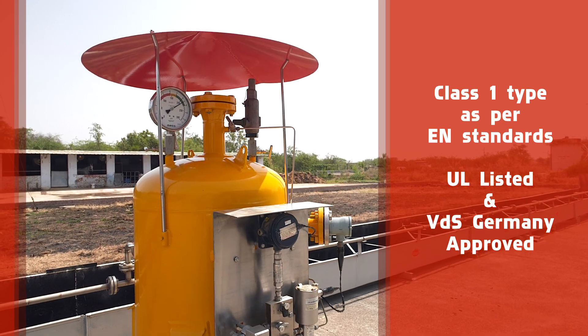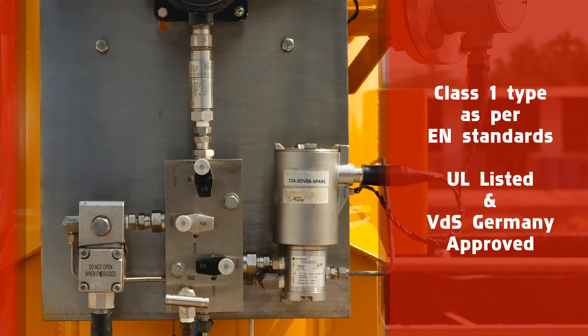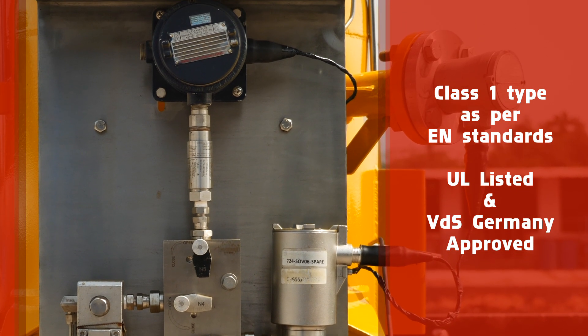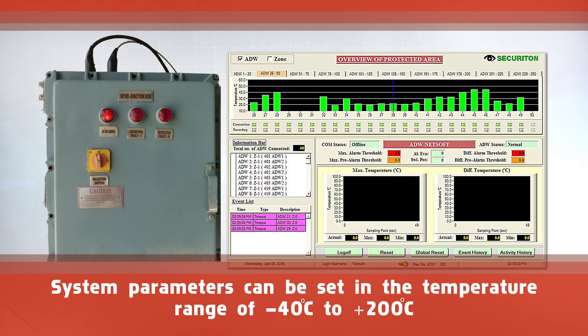The linear detection system is Class 1 type as per EN standards, UL listed and VDS Germany approved, with an inbuilt self-diagnostic system to check the internal health of the system. System parameters can be set as per site conditions.